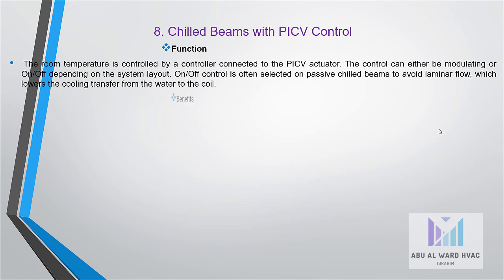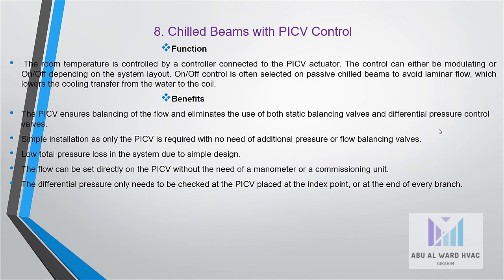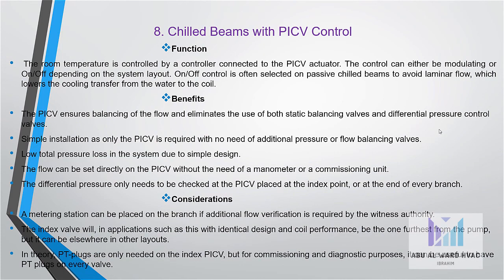Benefits: the PICV ensures balancing of the flow and eliminates the use of both static balancing valves and differential pressure control valves. Simple installation, as only the PICV is required with no need of additional pressure or flow balancing valves. Low total pressure loss in the system due to simple design. The flow can be set directly on the PICV without the need of a manometer or a commissioning unit. The differential pressure only needs to be checked at the PICV placed at the index point or at the end of every branch.